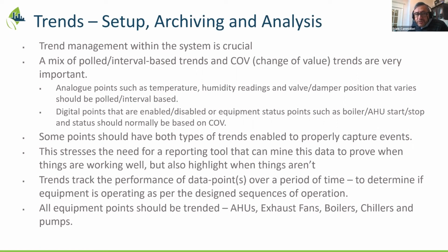I can tell you from personal firsthand experience, most of the time a BAS provider will go in and program it, but if they don't have a verification process - and many don't, that's just the reality of it - they don't use trend logs. Demand that they do. When you get sequences of operation and they indicate they've implemented it, say show me proof - that's where trends come in. Show me proof through trends that it's actually working as intended. I heard Adam say that, and Dave harp on that as well. This is an important thing to keep in mind.